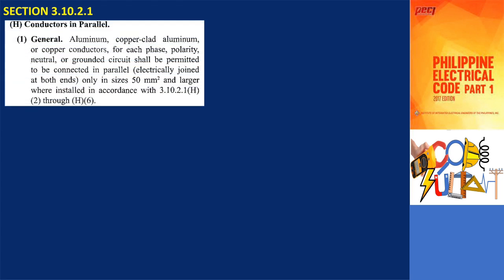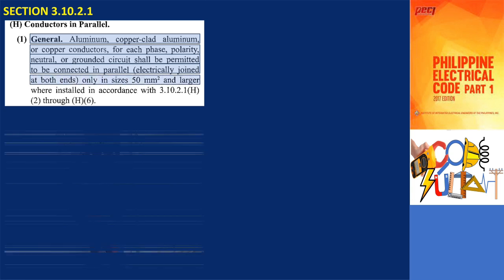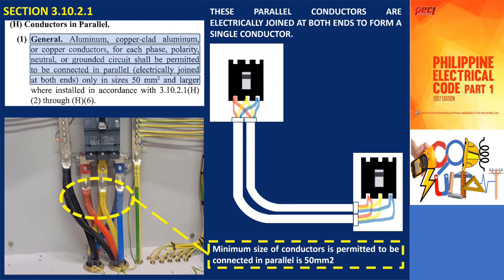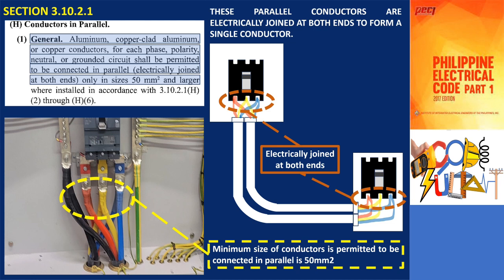Section 3.10.2.1h provides specific information and requirements for the paralleling of conductors and should certainly be the first reference that every electrical practitioner would choose for an understanding of the basics of paralleling conductors. This subsection permits aluminum, copper-clad aluminum, and copper conductors that are at least 50 square millimeters or larger to be connected in parallel, if these parallel conductors are electrically joined at both ends to form a single conductor.